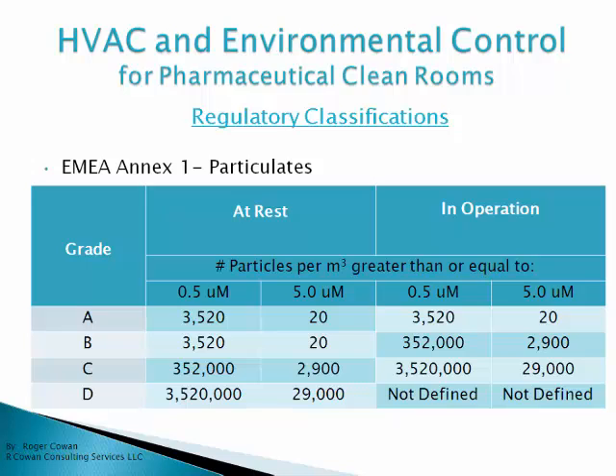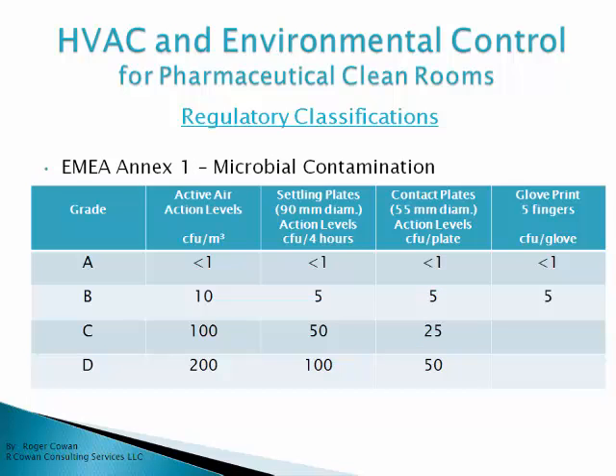EMEA Annex 1 provides specifications for both at rest and in operation conditions. For grade A — approximately equivalent to ISO class 5 — the limit is not more than 3,520 particles per meter cubed of 0.5 microns in diameter. They also have specifications for 5-micron particles. EMEA additionally has specifications for microbial contamination.